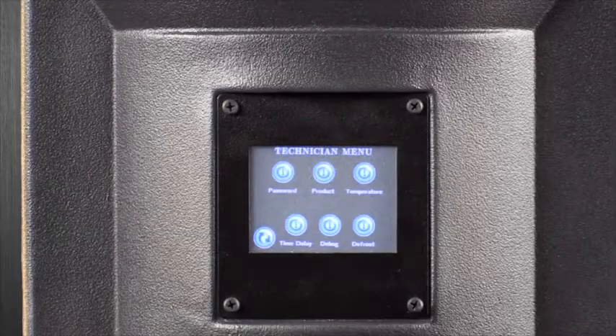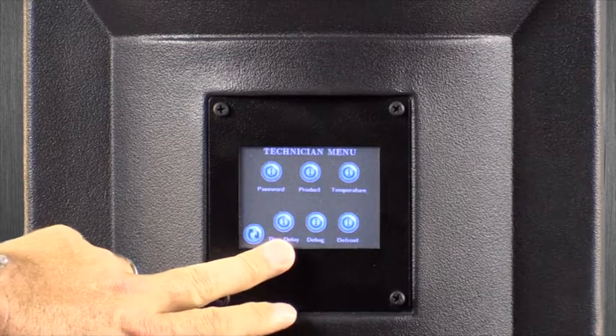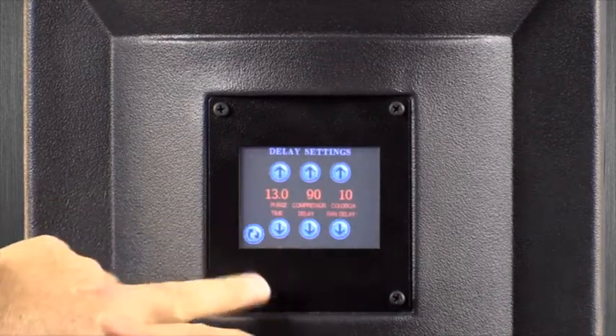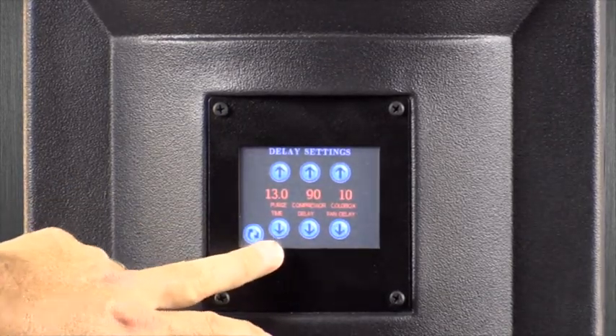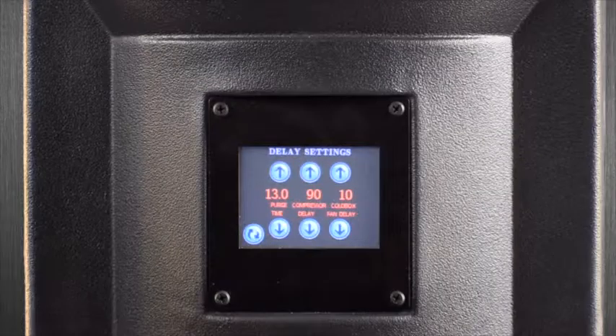Once you have returned back to the main technician menu, we will then select the time delay icon located on the lower left of the display. It will show 3 settings. Purge time. This will show how long the main rotor pump assembly will cycle in seconds. The compressor delay. This allows the machine, once it's powered up, not to activate the actual compressor for 90 seconds.